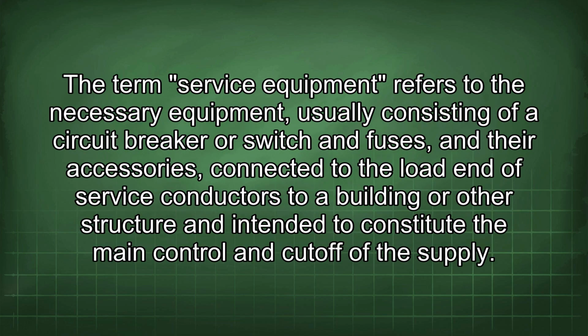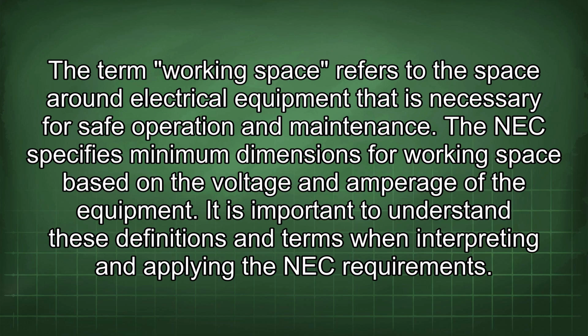The term "service equipment" refers to the necessary equipment, usually consisting of a circuit breaker or switch and fuses, and their accessories, connected to the load end of service conductors to a building or other structure and intended to constitute the main control and cutoff of the supply. The term "working space" refers to the space around the electrical equipment that is necessary for safe operation and maintenance. The NEC specifies minimum dimensions for working space based on the voltage and amperage of the equipment. It is important to understand these definitions and terms when interpreting and applying the NEC requirements.